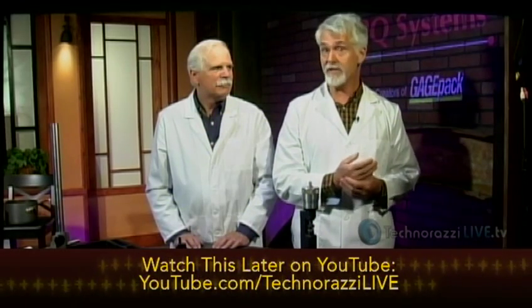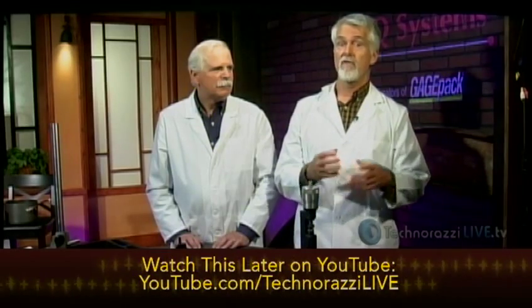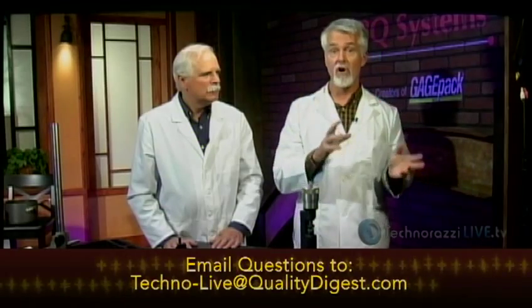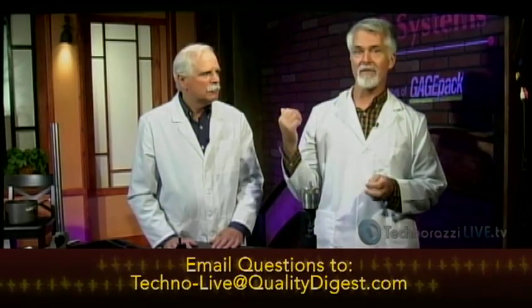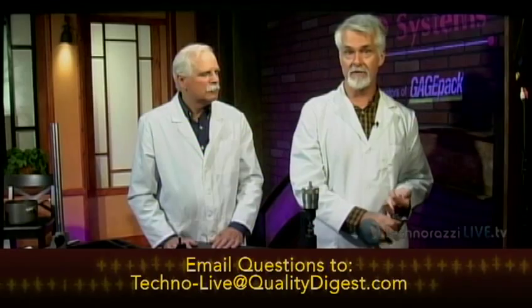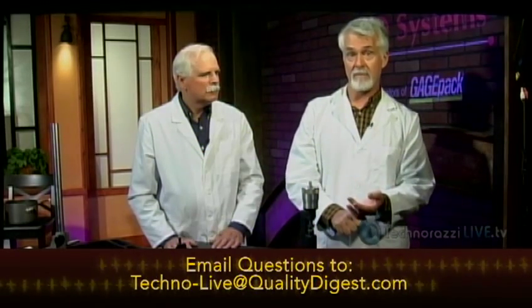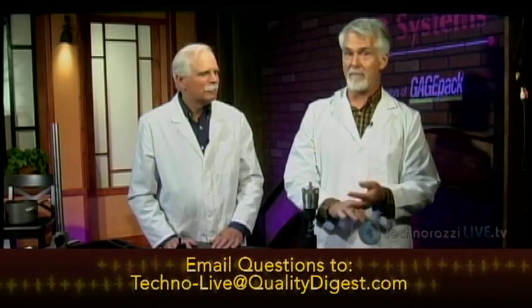Right. Recheck. And by the way, I'm not positive, but I believe it's a requirement if you're ISO 9001 registered that you have a process in place for if you have an instrument that is out of calibration and you have products out in the field. I believe you need a corrective and preventive action to go with that situation, in terms of the disposition of any parts in stock that were inspected with that out of calibration equipment, and what happens with any parts that are out in the field. So it is really critical.